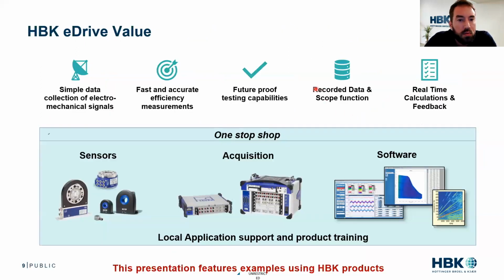At the end of the day, what we're really good at is measuring electric and mechanical signals in one place—you can look at your inverter voltages, currents, torque, speeds, accelerometers, and microphones all together. We make really fast and accurate efficiency measurements for things like flight cycles, and we can expand to really high channel counts, so you're effectively future-proofed. If today you need 20 channels but tomorrow you need 50, we can help you expand.